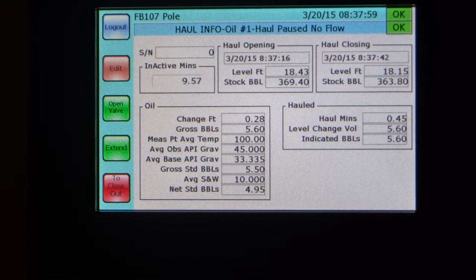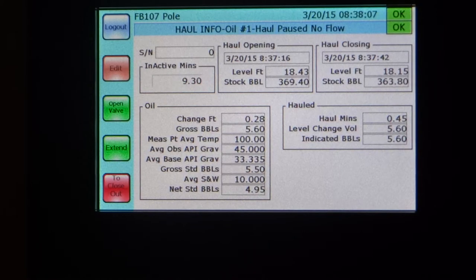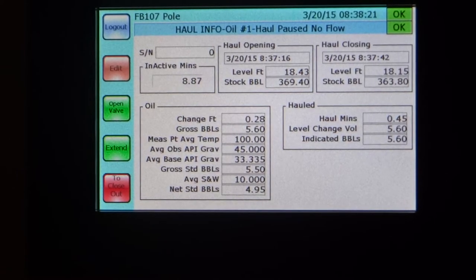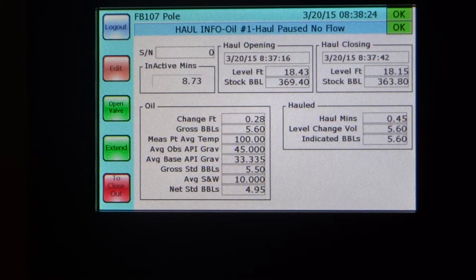The demo actually allows it to range up to 5.6 in this particular case. But even in reality, you would tend to get a value slightly higher than your preset because there is some time involved in shutting the system down. The unit will always record the amount of actual oil moved. You can see the various calculations already done — gross standard barrels available, we took the S&W percent of that and came up with net standard barrels, all of which can be brought up through a SCADA system.